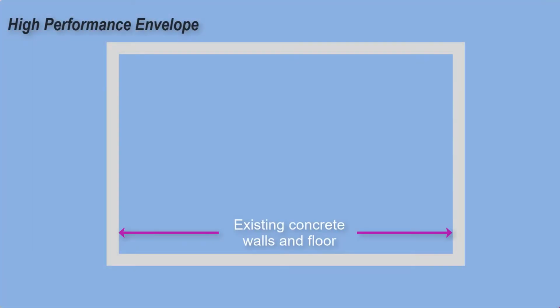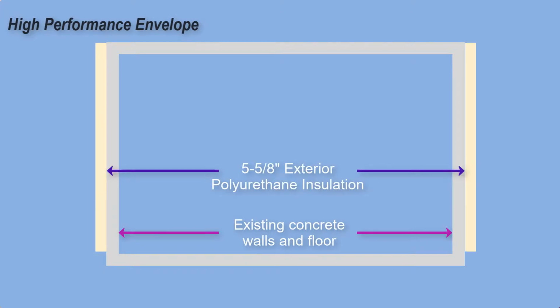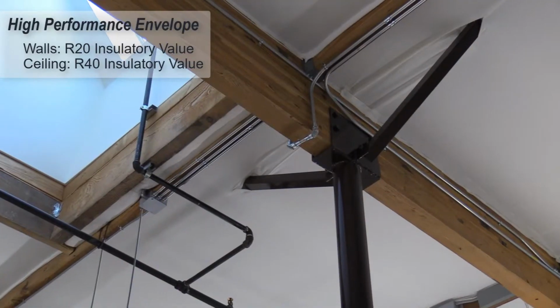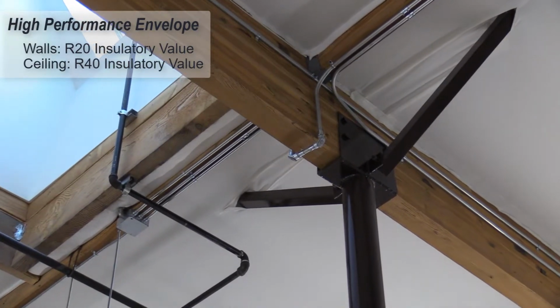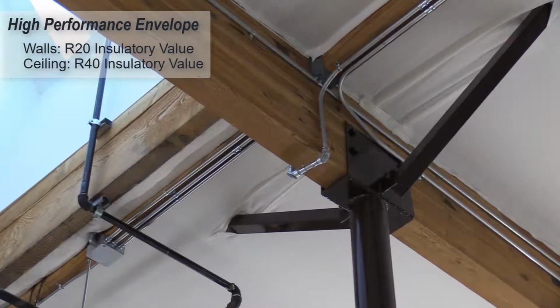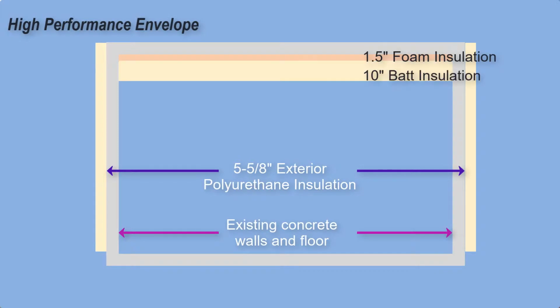We reduce the HVAC loads by insulating the building extremely well. Having a high performance envelope is probably the most important thing we did to the building. We put 5 5/8 inches of insulation on the outside, which keeps the concrete thermal mass available to be our air conditioner. That gives us about an R20 insulation value on the walls, combined with our electrochromic glass. On the ceiling, we sandwich thermal breaks from the solar panels with 1.5 inches of foam on top and 10 inches of batt underneath, giving us about an R value of R40. So that gives us a very high performance envelope to start with.